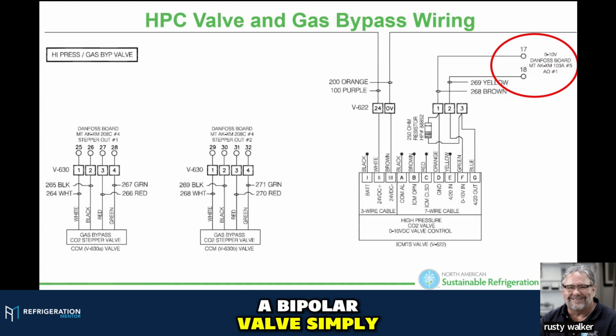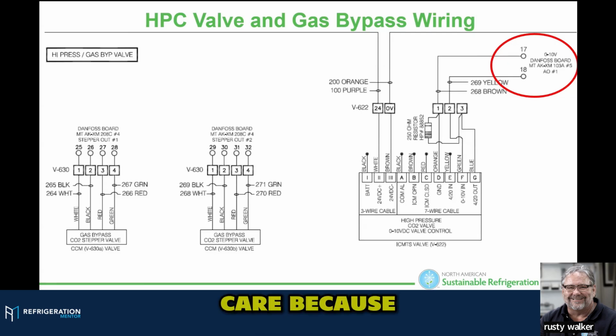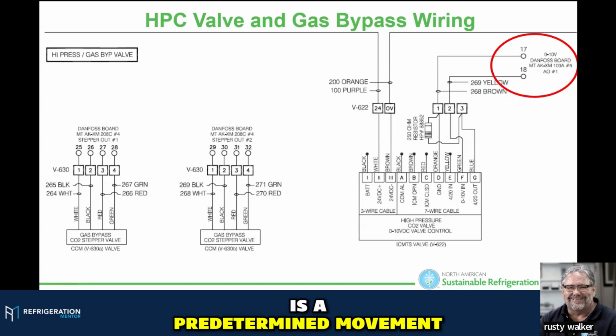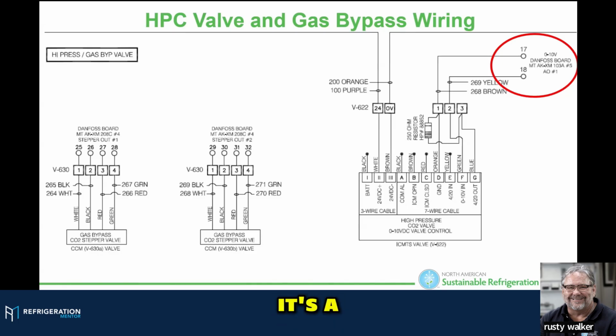A bipolar valve simply means - we all know how many steps, but I don't care how many steps. I really never do, because a step is just a predetermined movement. When the controller, the iPro, whatever, sends a signal to it, it's a predetermined amount of movement on the rotors and stators to move that valve positively or negatively. So all a step means is the predetermined amount, unless I'm programming - if I'm programming, I care. But as a technician, I just want to know if it works. I don't care what the steps are.